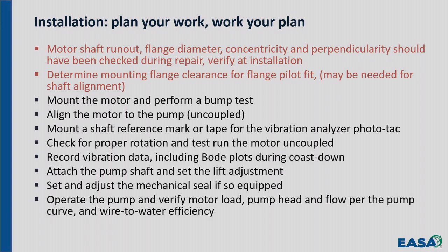So the next thing is to mount and perform a bump test. This is the motor sitting on the pump. You did the bump test when it was bolted down on the test stand. This is much more important than that. You have to do this bump test.